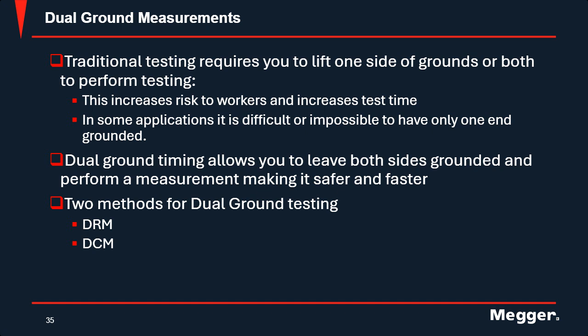In some applications, it's difficult or impossible to have only one end grounded. But dual ground timing allows you to leave on both sides of your grounds and perform the measurement, making it safer and faster. So there are two methods that you can use for dual grounding. There's dynamic resistive measurement, which is DRM, or dynamic capacitive measurement, which is DCM. We're going to talk about both. We're going to talk about DCM first. It's the better of the two options. You do get a timing.